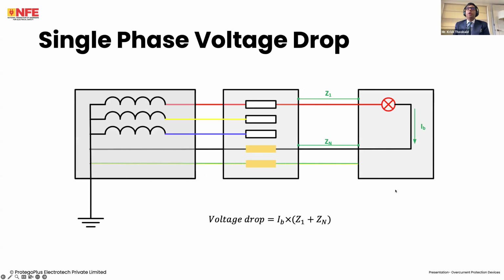Now, what does this look at? If we look at a single phase piece of equipment, our voltage drop is going to be affected by, if this is the point of commencement of supply, this is our distribution board, this is our load, the impedance of the line conductor and the neutral conductor. So in effect, the voltage drop is simply the design current multiplied by the sum of these two impedances. This is just the equipment. So how much voltage is dropped because it is being supplied through these conductors, essentially.